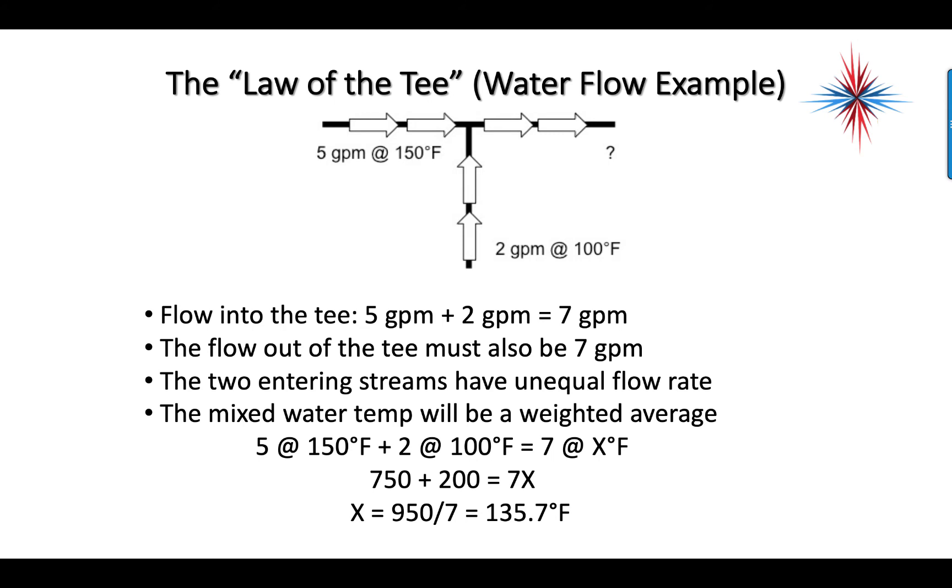We're solving for X. We multiply five times 150 - that gives me 750. We multiply two times 100 - that gives me 200. Still equals 7X. Yes, I'm going back to high school algebra here. To solve for X, you have to do the same thing on both sides. We add 750 and 200 together because there's no X's or letters after them - comes up with 950. To get rid of this seven, I have to divide both sides by seven. So X is 950 divided by seven, equals 135.7 degrees is my mixed water temperature. Got to use a little bit of algebra here. Who said high school math will never be used in the future? You do use it.